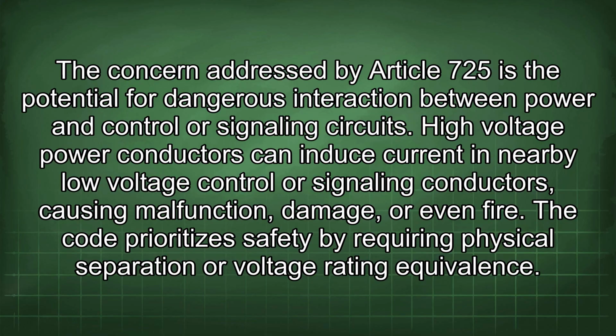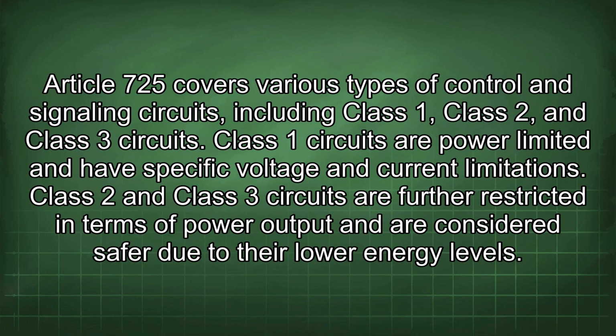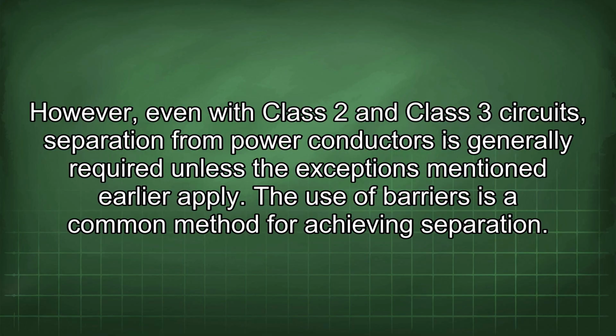The concern addressed by Article 725 is the potential for dangerous interaction between power and control or signaling circuits. High-voltage power conductors can induce current in nearby low-voltage control or signaling conductors, causing malfunction, damage, or even fire. The code prioritizes safety by requiring physical separation or voltage rating equivalence. Article 725 covers various types of control and signaling circuits, including Class 1, Class 2, and Class 3 circuits. Class 1 circuits are power limited and have specific voltage and current limitations. Class 2 and Class 3 circuits are further restricted in terms of power output and are considered safer due to their lower energy levels. However, even with Class 2 and Class 3 circuits, separation from power conductors is generally required unless the exceptions mentioned earlier apply.